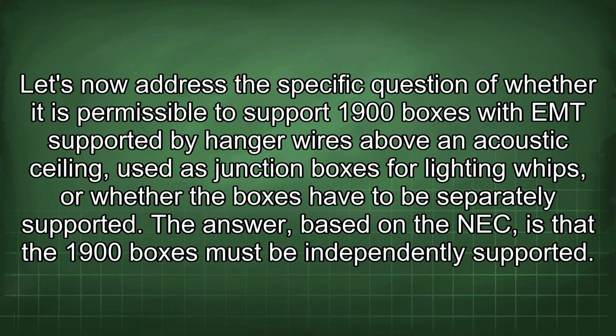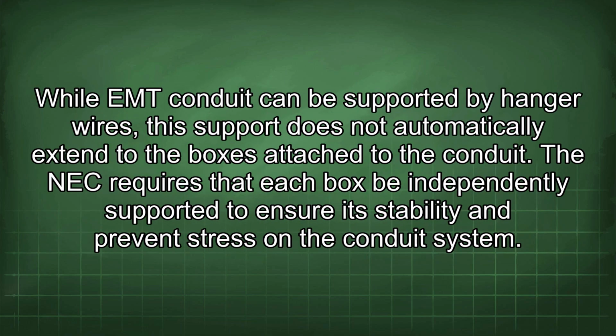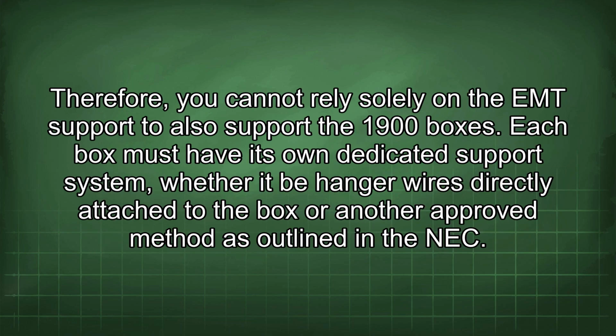Let's now address the specific question of whether it is permissible to support 1900 boxes with EMT supported by hanger wires above an acoustic ceiling used as junction boxes for lighting whips, or whether the boxes have to be separately supported. The answer, based on the NEC, is that the 1900 boxes must be independently supported. While EMT conduit can be supported by hanger wires, this support does not automatically extend to the boxes attached to the conduit. The NEC requires that each box be independently supported to ensure its stability and prevent stress on the conduit system. Therefore, you cannot rely solely on the EMT support to also support the 1900 boxes.